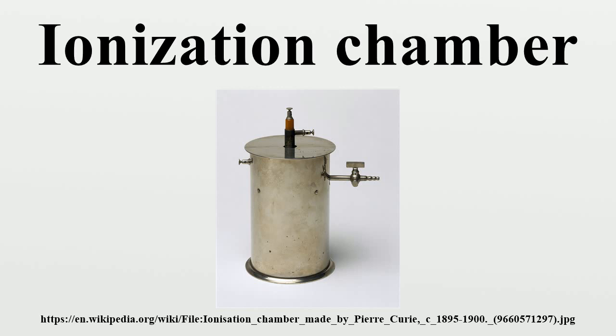Conventionally, the term ionization chamber is used exclusively to describe those detectors which collect all the charges created by direct ionization within the gas through the application of an electric field. It only uses the discrete charges created by each interaction between the incident radiation and the gas, and does not involve the gas multiplication mechanisms used by other radiation instruments, such as the Geiger-Müller counter or the proportional counter.